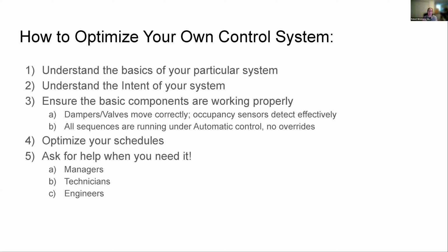You can check this—you know how to run overrides within your building. Go through and check things periodically. When you've got somebody who's out of the office and you know it, go into that space, calibrate the temperature sensors, check for your airflow sensors if you have an air hood. Make sure that your tools are also within reasonable calibration.